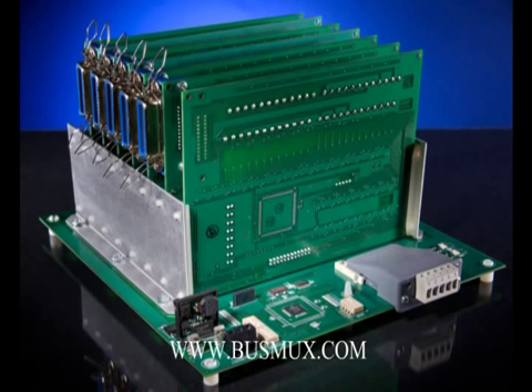The hardware consists of a motherboard that houses the communication adapter of your choice and up to 8 input cards. Each card can handle up to 24 inputs for a total of 192. Remember, however, these motherboards can be daisy-chained together for an unlimited number of inputs.